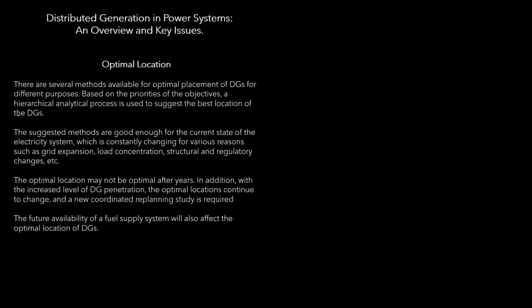Optimal location. There are several methods available for optimal placement of DGs for different purposes. Based on the priorities of the objectives, a hierarchical analytical process is used to suggest the best location of the DGs. The suggested methods are good enough for the current state of the electricity system, which is constantly changing for various reasons such as grid expansion, load concentration, structural and regulatory changes, etc. The optimal location may not be optimal after years. In addition, with the increased level of DG penetration, the optimal locations continue to change, and a new coordinated replanning study is required. The future availability of a fuel supply system will also affect the optimal location of DGs.